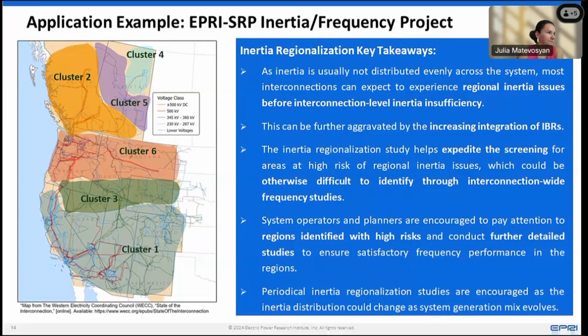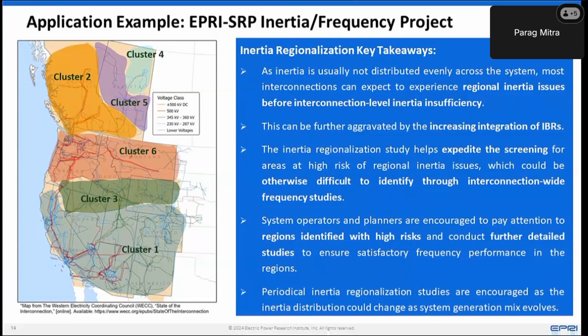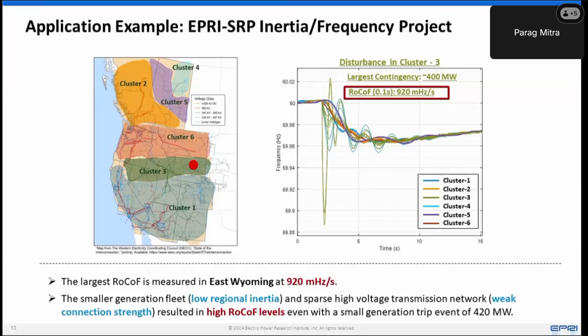The grouping doesn't depend upon contingencies, but the risk depends on, within each cluster, what is the possible largest loss of generation in-feed. That's what we call SLI, single largest in-feed. It just has to be the largest credible outage. It doesn't mean it has to be the outage of a single generator, a single plant, or a single HVDC link, but whatever is the credible largest in-feed loss. You can go back and look at historical data, or look at your protection arrangement, to figure out what that could be, and that's how it's defined.